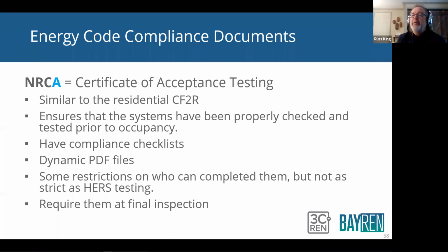So we do the same thing to buildings. You don't just build it, install it, and let the people move into it. You've got to test it out. And so part of that commissioning process is testing the controls, testing the airflow, making sure it works. Some of those tests can be done by the installers if they're certified to do it, and some of those tests have to be done by a third party. The ones that can be done by the installer are called acceptance tests.